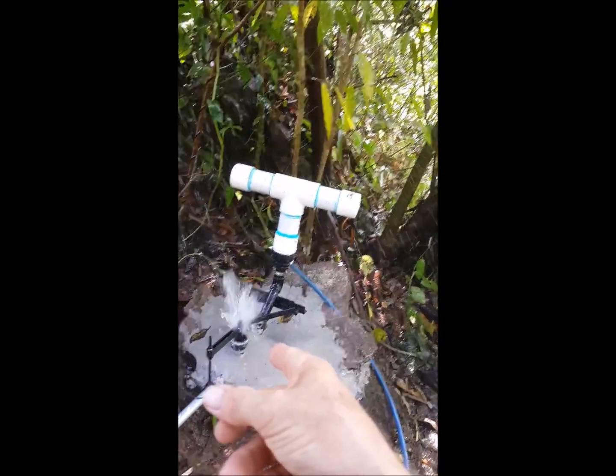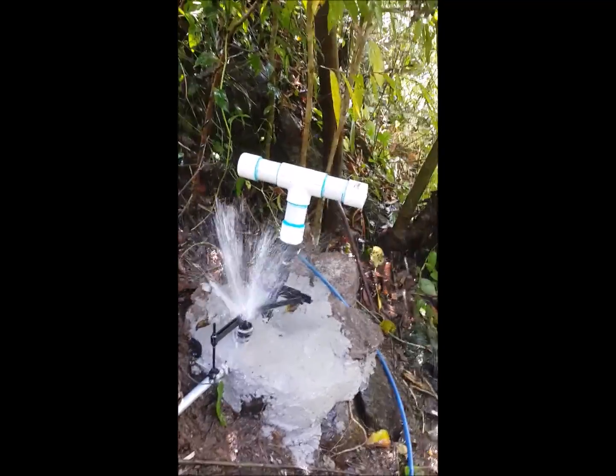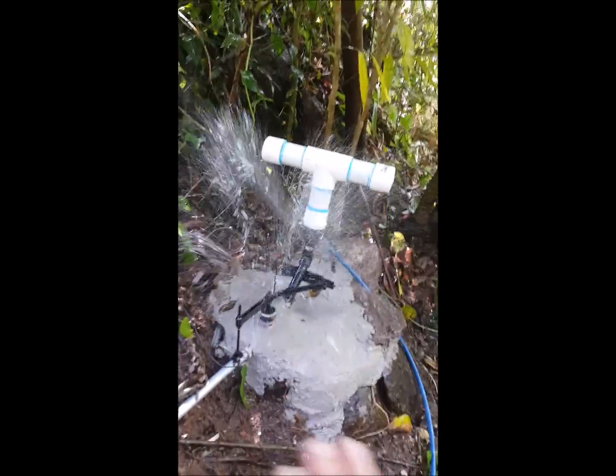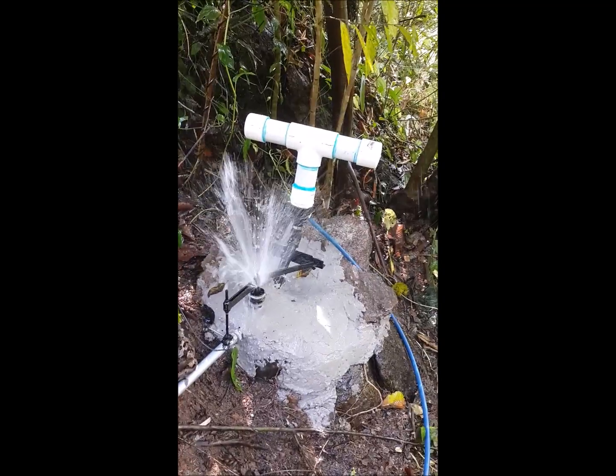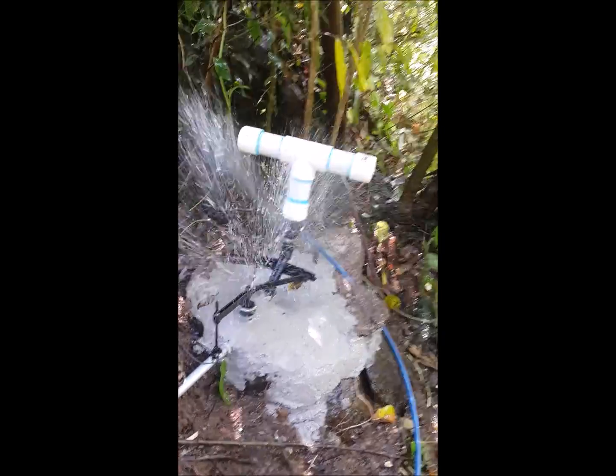And it's pretty simple to change it. You know, a couple hours to change the rubber there. And that's basically all the maintenance. Occasionally they need to be adjusted. There's full adjustment on the seating on that valve, so you can adjust it basically perfectly. It's a very low maintenance system. One I've installed of this same size has been operating for almost 5 years with no problems.